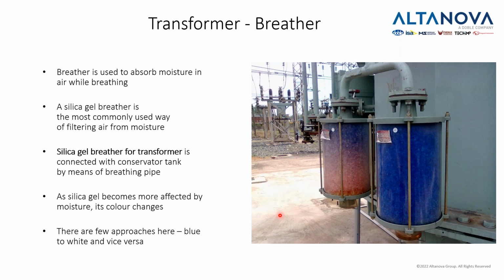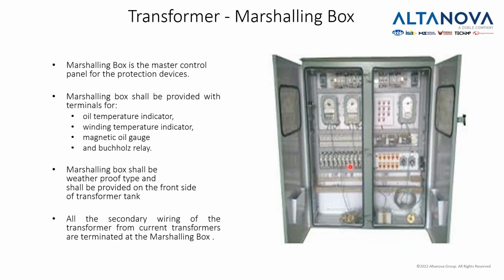All the air which enters the transformer enters through this silica gel, through the breathers, and the breathers have different philosophies regarding color. In this case, you see the blue one means that it's okay, and the white one means that it's starting to degrade. So it's starting to become too wet. There are different approaches, depending on which part of the world you're situated in. We have the marshalling box, which is a box which basically controls your power transformers.